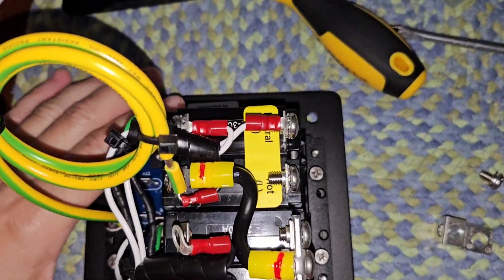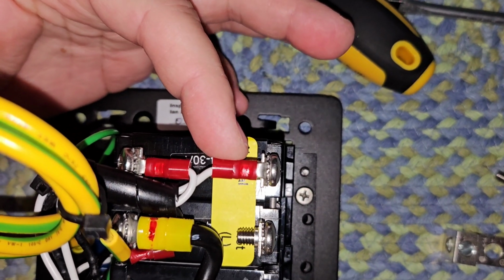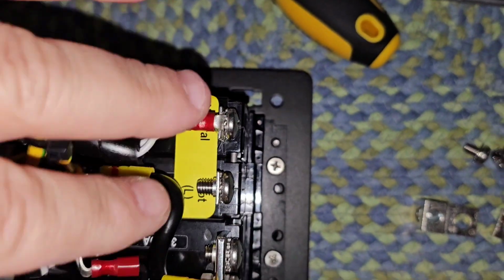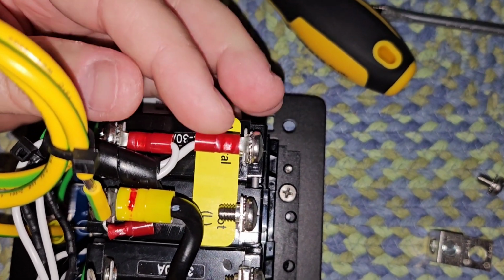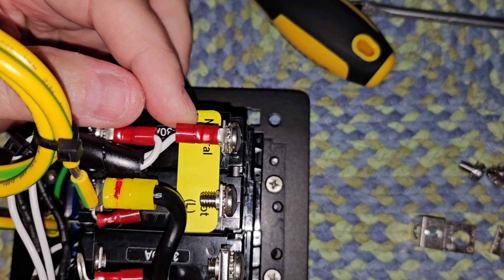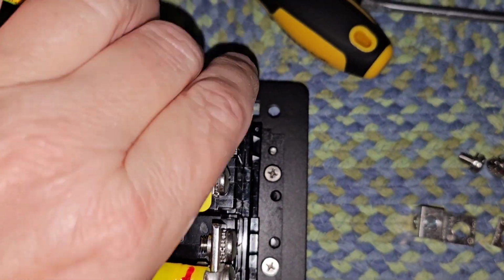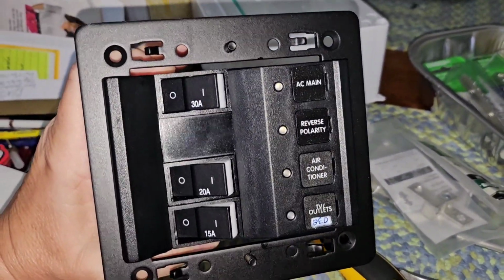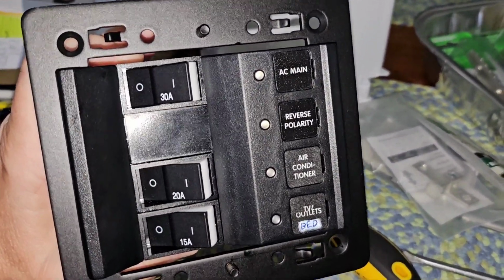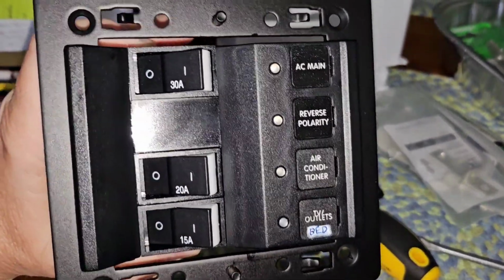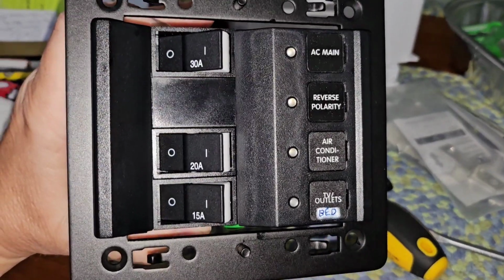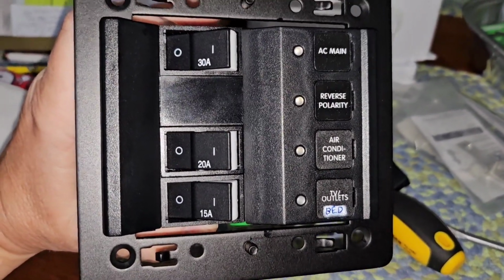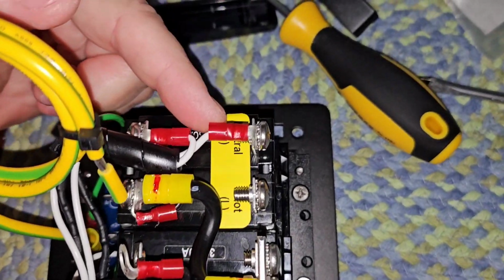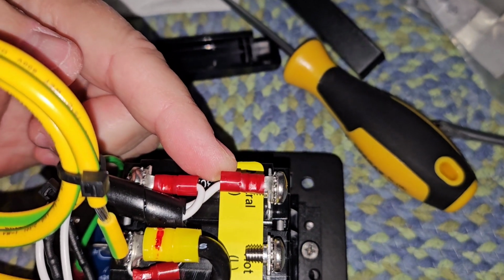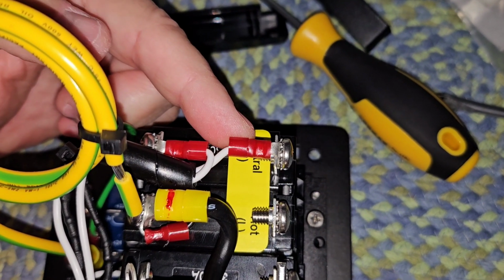This is the neutral from the 30 amp. These two terminals make up the 30 amp new main AC breaker that will go on the output of my 3000 watt inverter. Basically this is like a little sub panel I'm adding to the output of my 3000 watt inverter. The input's already protected by a 30 amp circuit breaker, so I'm putting the output on this 30 amp circuit breaker so I can add these two separate circuits and have them all protected.